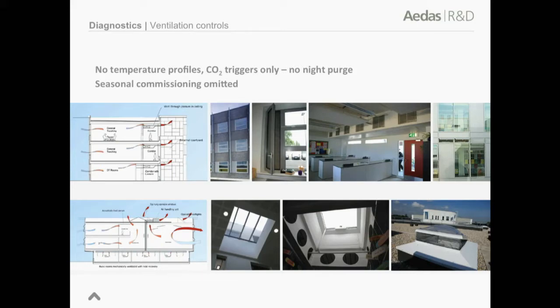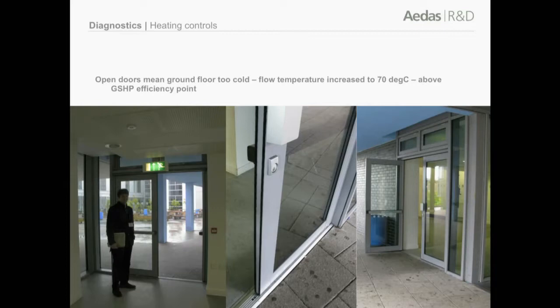But what was clear is that after a few questions, the night purge wasn't working in the building - it wasn't properly configured. In fact, I haven't come across a single building in all the studies of the 14 buildings I've seen where seasonal commissioning wasn't somehow value engineered during the contract. So without the night purge and without the proper temperature profiles from the seasonal commissioning, the building ended up opening the windows at all the wrong times and having to use a lot more heating.